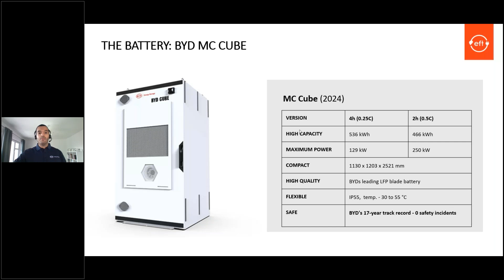And the interesting thing about that cube concept is that, again, it has the blade cell and the blade-to-system design. So the cells are put directly into the cabinet. The whole MC Cube is very compact, with around 500 kilowatt hours in such a small space. And it's possible to scale those cubes in different numbers. So it starts with around 500 kilowatt hours, but you can have up to 10 of those in a 20-foot container, which gives you around 5 megawatt hours.